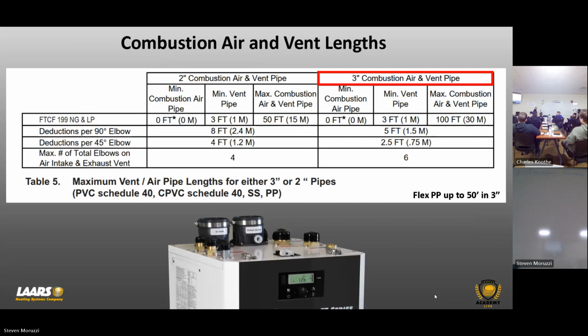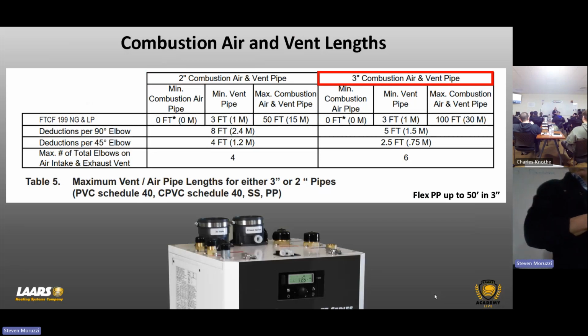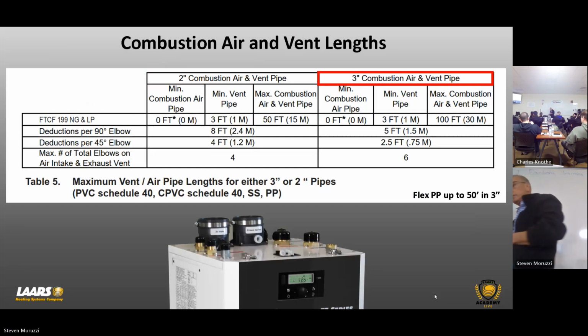All right. So don't forget, if I've got 40 linear feet of exhaust and I have 4 fittings, all right, then that's 4 times 8. That's another 32, right? So instead of 40, I have 72. So don't just measure your linear pipe, okay? You got to calculate in your elbows. So in that example, go 3-inch, which would give you the 3-inch collar right off the top of these heaters, okay? So yes. Is that a combined or an individual? Individual, thank you. Each.